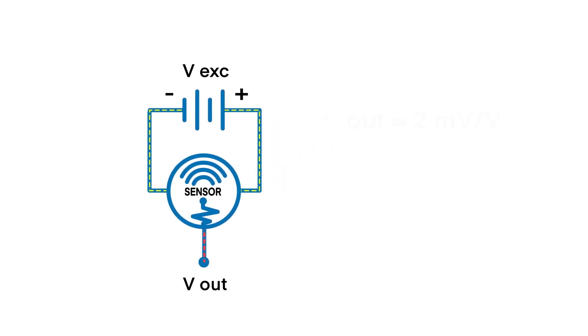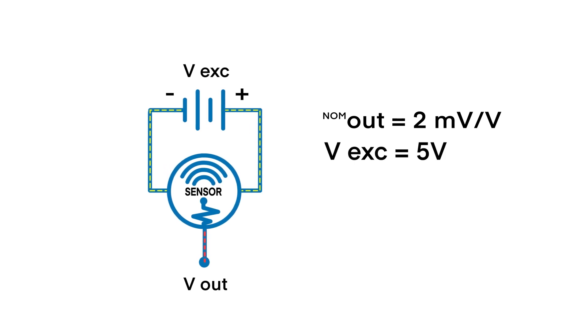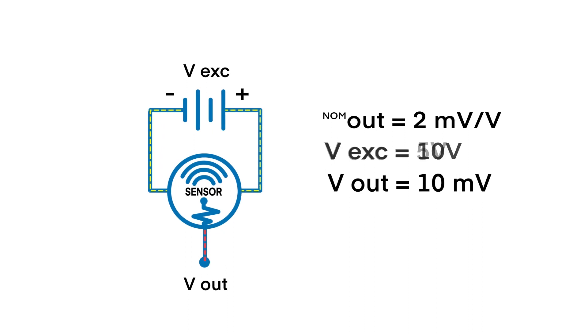For example, a sensor with a nominal rated output of 2 millivolts per volt excited with 5 volts will provide a nominal voltage output of 10 millivolts, whereas 10 volts excitation will result in a nominal voltage output of 20 millivolts.